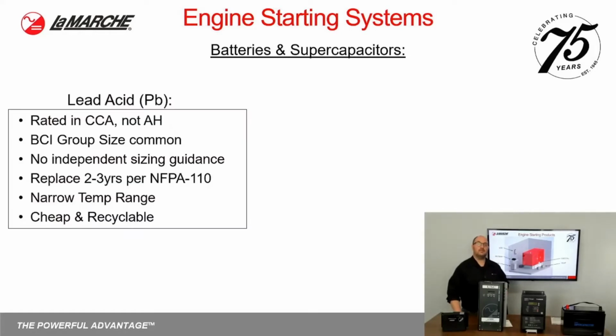So let's talk a little bit about batteries for the system. What's far and away most common in this market segment is a lead acid battery. I've got PB here for the lead. The lead acid battery is rated in cold cranking amps, but typically not associated with an amp hour rating. So that can cause some confusion. They're normally in a BCI group size, similar to the batteries under the hood of your car. Those are all different group sizes. So what they don't give you in this market is independent sizing in terms of how many cold cranking amps you generally need for an application.